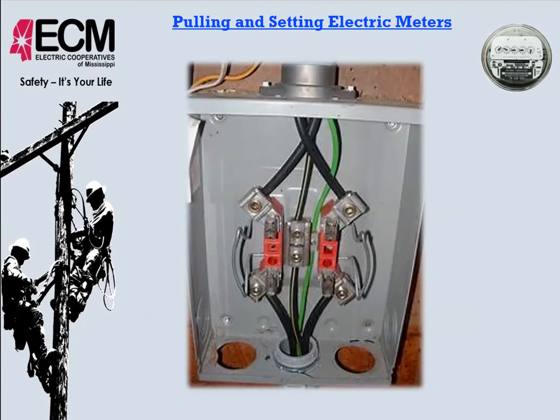Okay, here's another decent meter base here. Things hooked up right. This is going to be some underground cable like we would run from our transformer out to our meter base. It has an orange stripe and a yellow stripe on it, kind of to help identify it from one end to the other. And then you also see the appliance ground here. If it is running inside the same pipe, it does have to be insulated. Everything inside the pipe has to be insulated, kind of to keep it from rubbing and chafing.